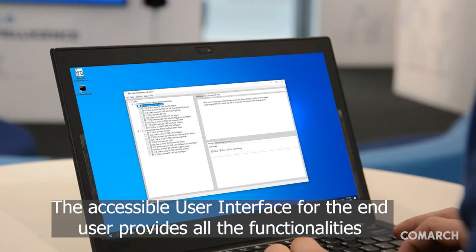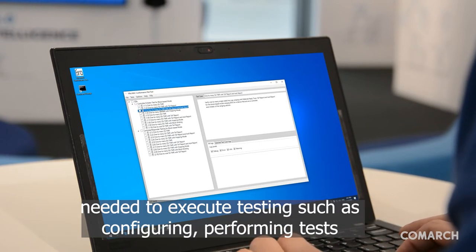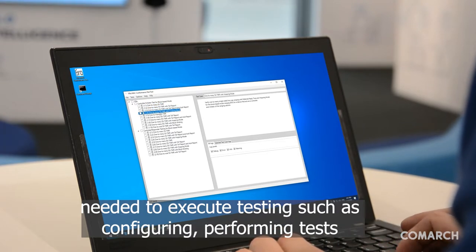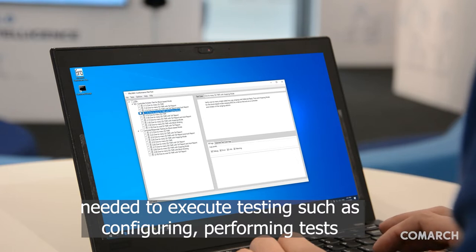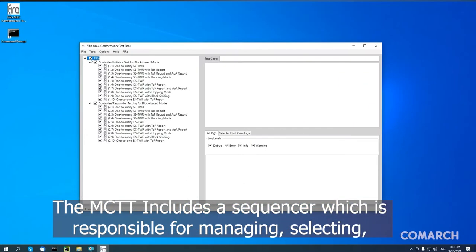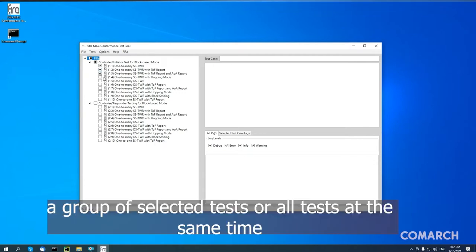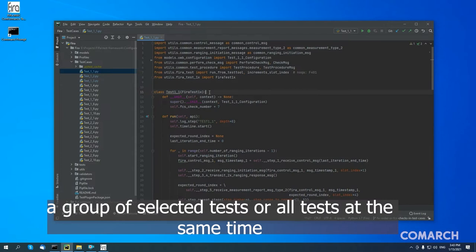The accessible user interface for the end user provides all functionalities needed to execute testing, such as configuring, performing tests, and presenting the results. The MCTT includes a sequencer, which is responsible for managing, selecting, and running test cases written in Python, and allows you to run a single test, a group of selected tests, or all tests at the same time.